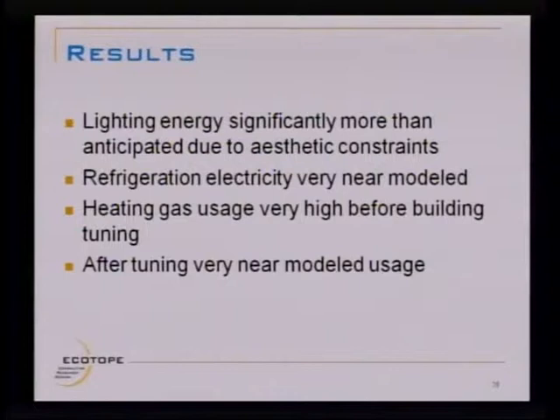Excuse me, do you know what kind of control system it was? Was it a step dimming or was it just on? No, it was just on off, but each fixture had 2 lamps, so they were able to either have 2 lamps on, 1 lamp on, or no lamps on. But each circuit was independently controllable.